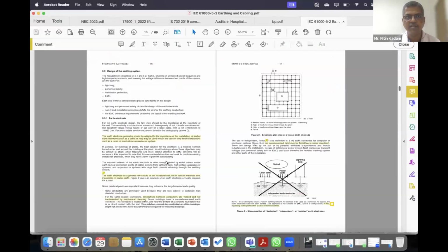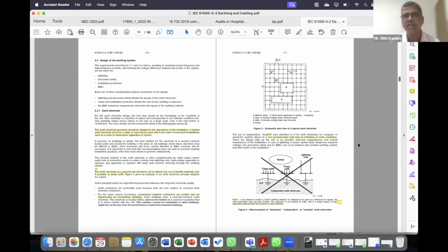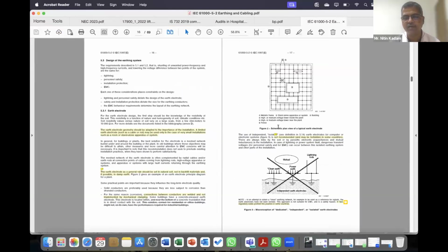It is recommended to have separate earthings for the elevator system, or rather from the secondary of the transformer to the MET of the building. From the MET, you take it directly to the elevator main switch, from where it can be distributed to the controller, inverter, machine, and so on. Okay.